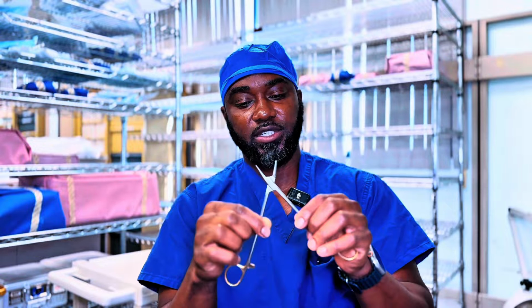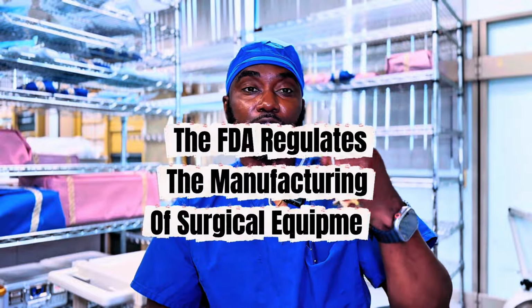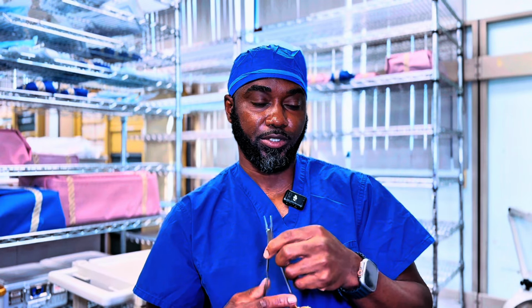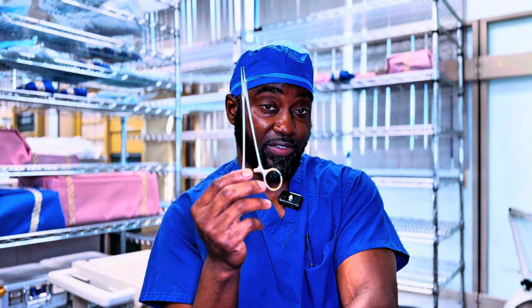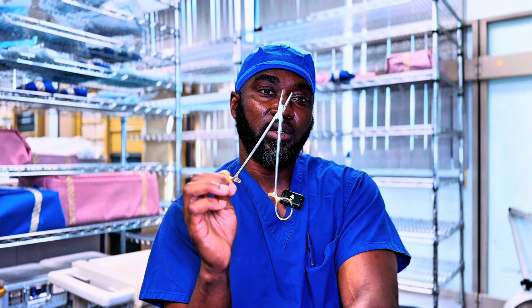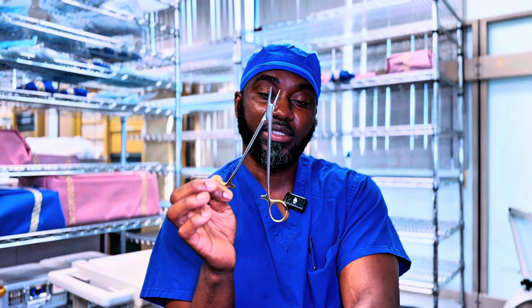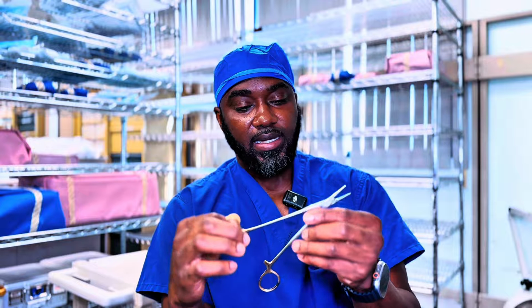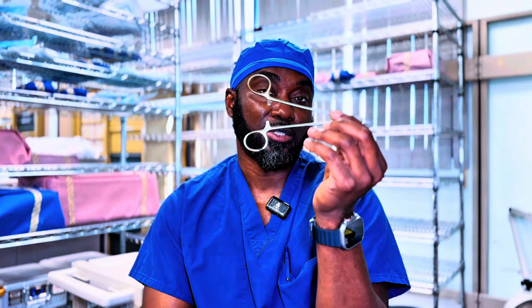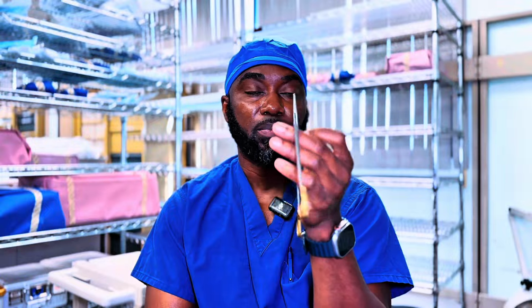When a medical device is designed or proposed for use, they have to go through the FDA, which will tell the company manufacturing the instrument to go through the 510K or the pre-market approval process. Under the 510K testing or pre-market approval phase, instrument manufacturers are required to test their instruments in independent labs. These labs will go through testing these instruments. All of that testing will be used by the end user after the instruments have been manufactured.